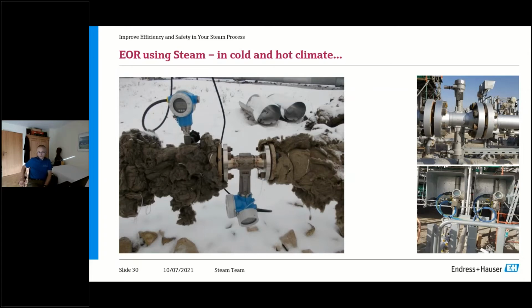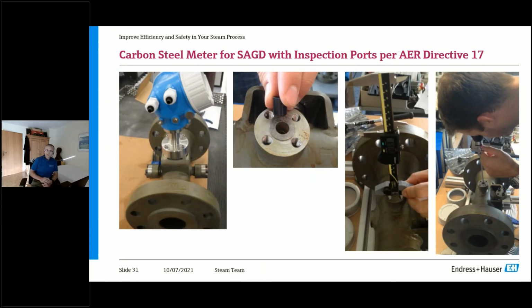Here an example also from the oil fields. This is distribution inside EOR, so enhanced oil recovery, where you're sending steam into the ground in order to make heavy oil more fluent, so to change the viscosity, and then you pump it out. The right-hand side is in the desert, so to speak. I think that's in Kuwait. The left-hand side is in Siberia. So we find those devices in a variety of climates. And here is a special meter we did for Canada, for SAGD, for the oil fields in Alberta. This is made of carbon steel with a special means to check the health of the meter body. But this is a requirement per AER Directive 17, so a local requirement in Alberta.